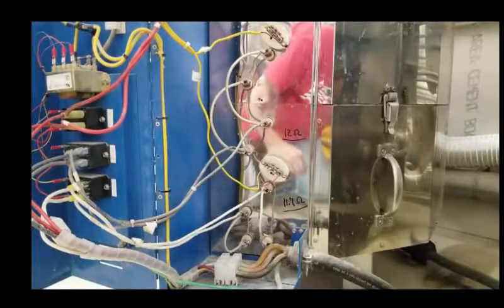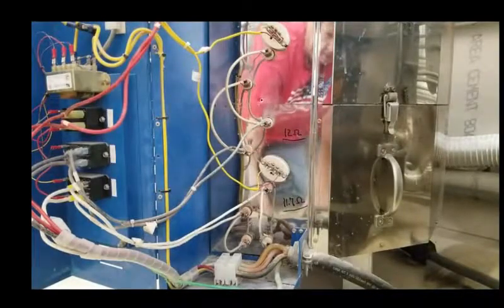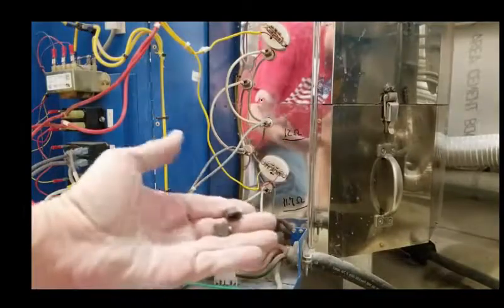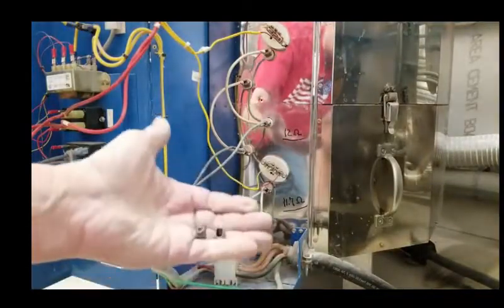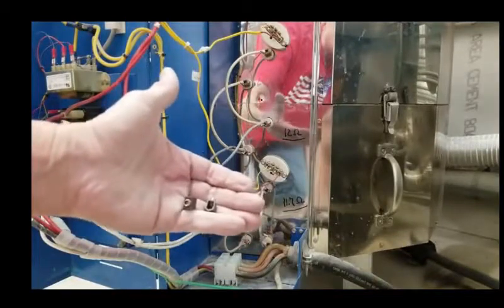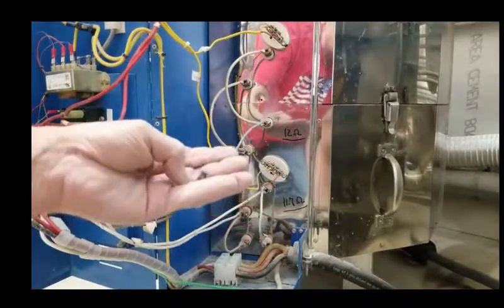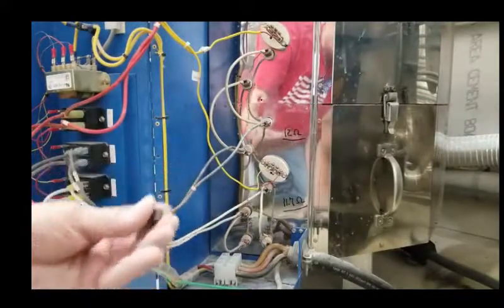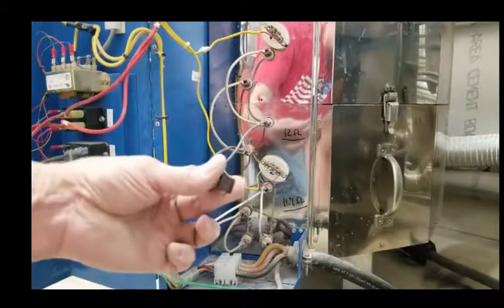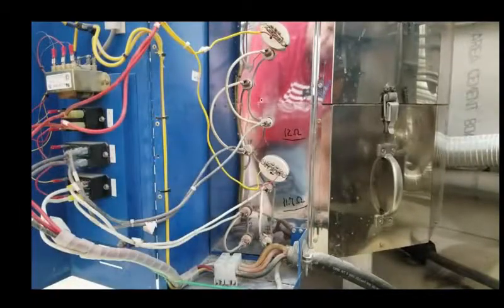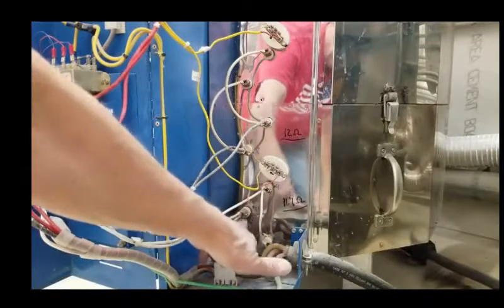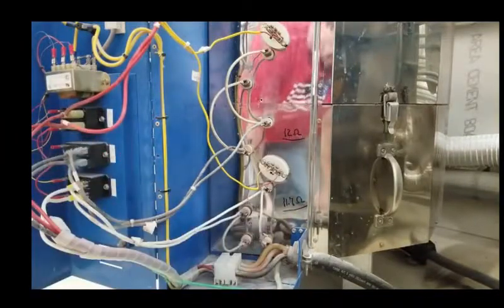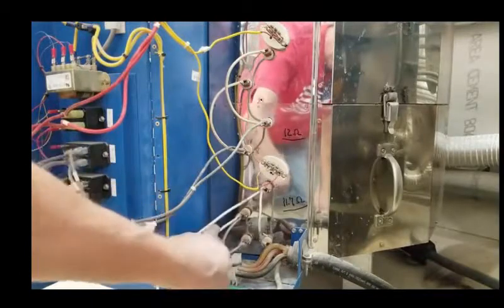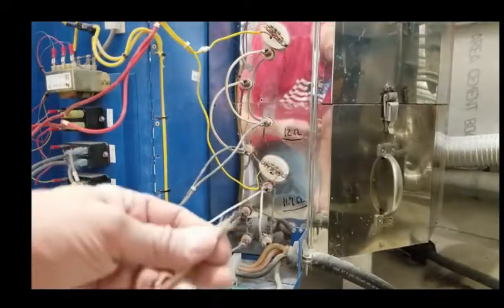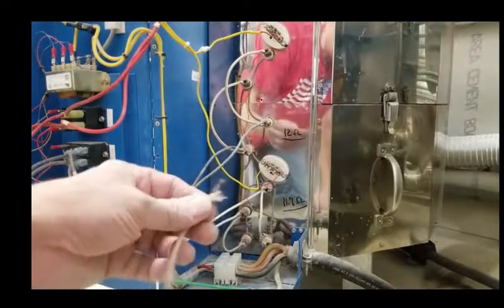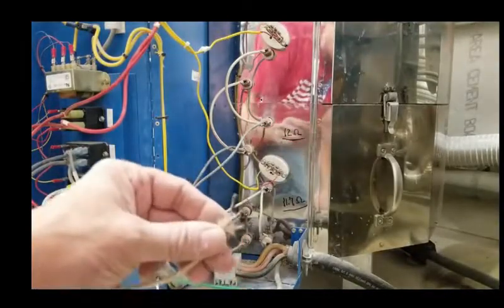All right, we are back again, and after closer examination, we found these two connectors. I don't know if I can get these to focus real well. They're pretty burned. They're much darker and corroded. And so that was one of our bad connectors. So we replaced this wire, and both connectors are nice new shiny copper. Tighten them down a whole bunch. We trimmed this wire back because this is what we found on the ends of our wires. They're quite burned, corroded, and brittle.